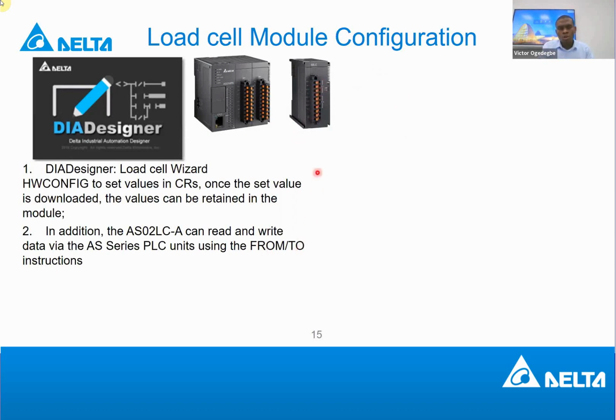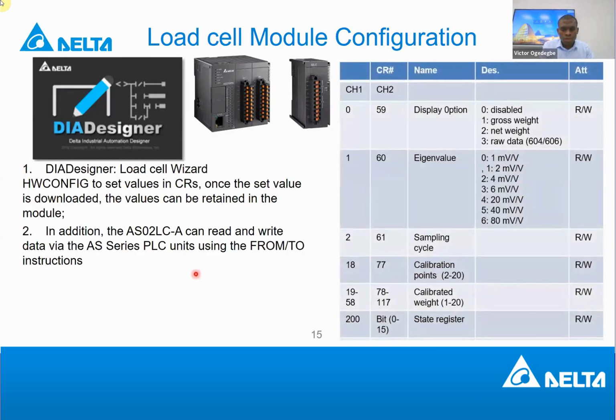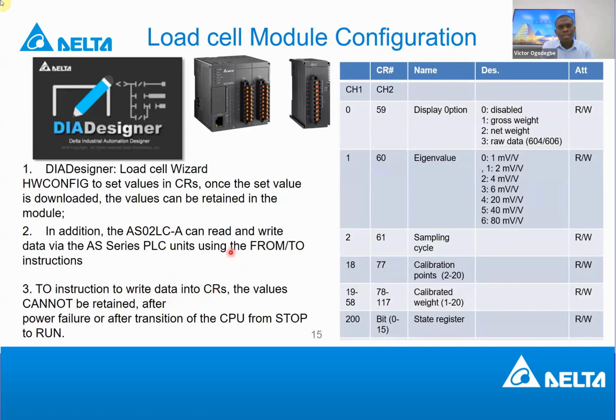So you use the TO instruction to write parameters to the module. Another important thing to note is that if you use the TO instruction to write, what you have written will not be retained. So if you lose power, or there's an accidental power off, what you have configured will be lost. So when you start up the PLC and trigger the application again, this instruction can rewrite those parameters back to the module. So these are basically the two ways you configure this module.